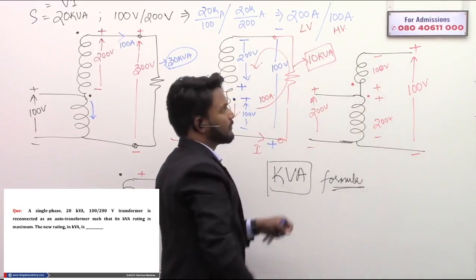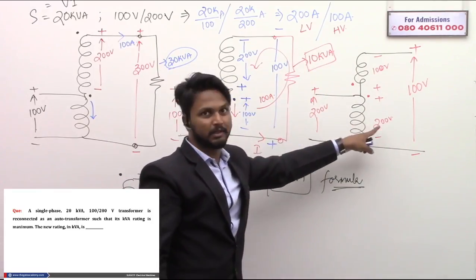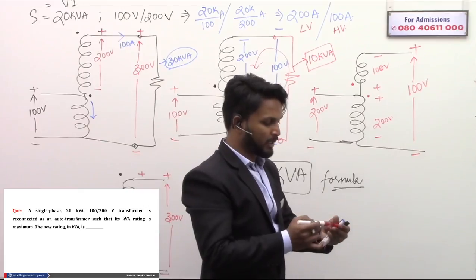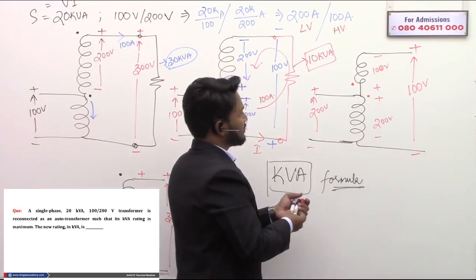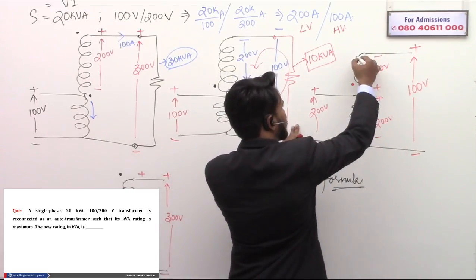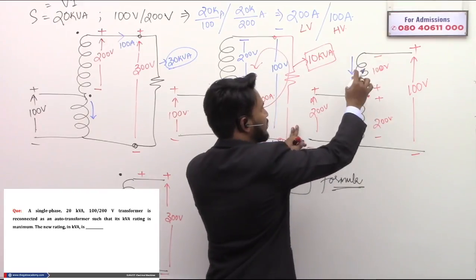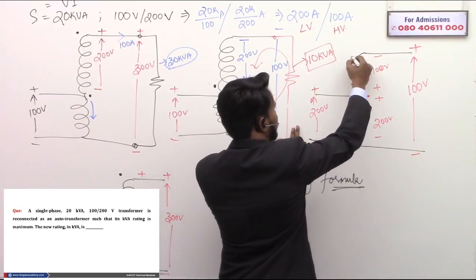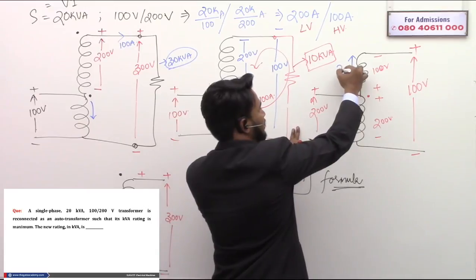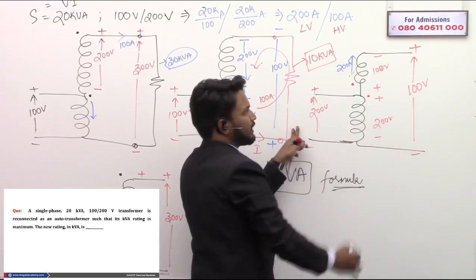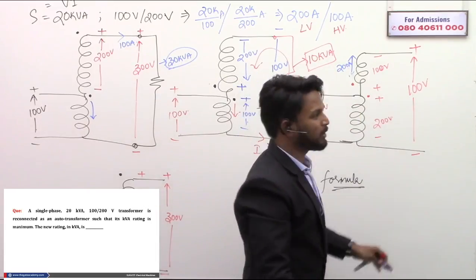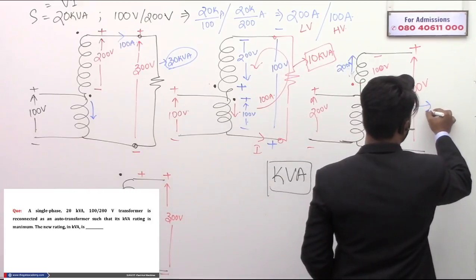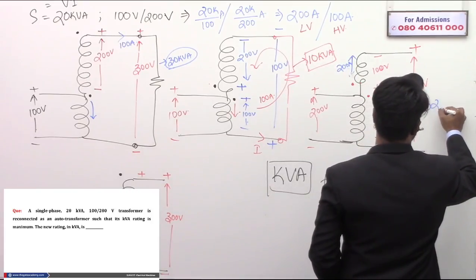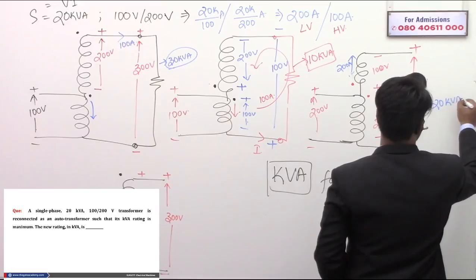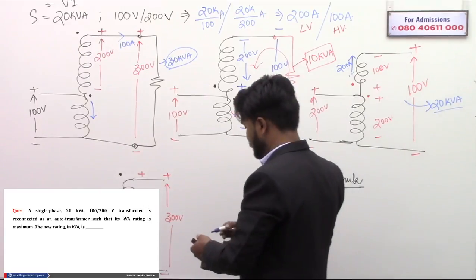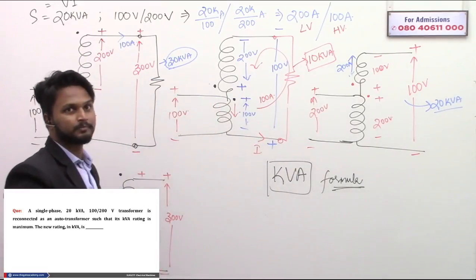10 kVA. Similarly, the rating of this configuration is 100 volts multiplied by how much current this LV winding can carry. This LV winding can carry a maximum current of 200 amperes. Therefore, 100 multiplied by 200, the rating of this configuration is 20 kVA.